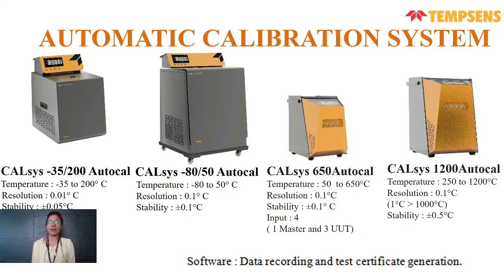Calsys 1200 AutoCal with temperature range 250 to 1200 degrees centigrade, resolution 0.1 degree centigrade, with stability plus minus 0.5 degree centigrade. In all our automatic calibration systems, we are providing a data recording facility with test generation and report facility.